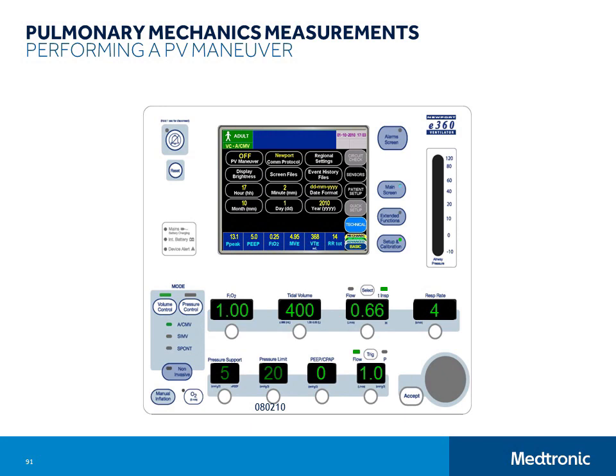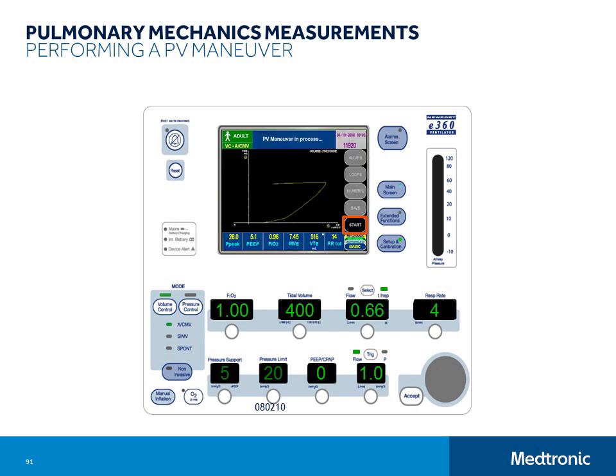The E360 PV maneuver automatically terminates when the manual inflation button is released, airway pressure reaches 60 centimeters of water (millibar), the high pressure alarm limit is violated, or 90 seconds elapse.